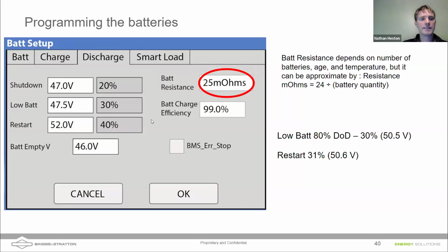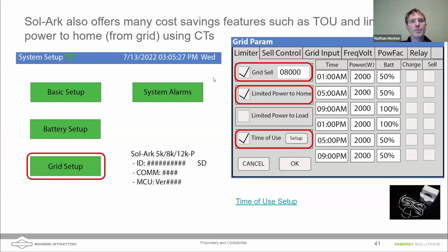And then the low battery settings, I've given you some guidelines on the right to what to set those to. Under grid setup, you have the ability to control a lot of things, such as time of use, limiting power to the home from the grid by using CTs, etc. And so this is overall a maximum limit of how much power you would be able to sell to the grid. You can limit the power to the home as well. So if you want to limit the power to the home, you can set those values.